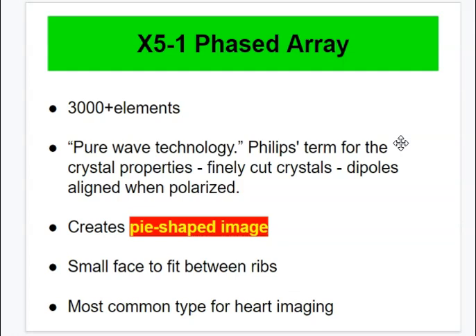They've developed something called PureWave technology, their term for the crystal properties in their transducer. These crystals, as you can imagine, had to be very finely cut because there are 3,000 plus crystals in their X5-1 transducer. Each piezoelectric material has what they call dipoles, and when the machine is turned on and the transducer is used, these dipoles are aligned when polarized. You don't have to know a whole lot about that, but just understand there's a lot going on in there, and as we know in the phased array, it creates this pie-shaped image, and as we said before, a very small face to help with fit between the ribs. And it's the most common type for heart imaging simply because of its characteristics in that regard.